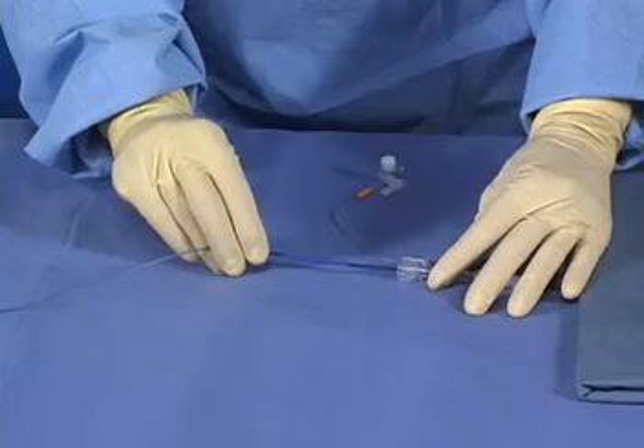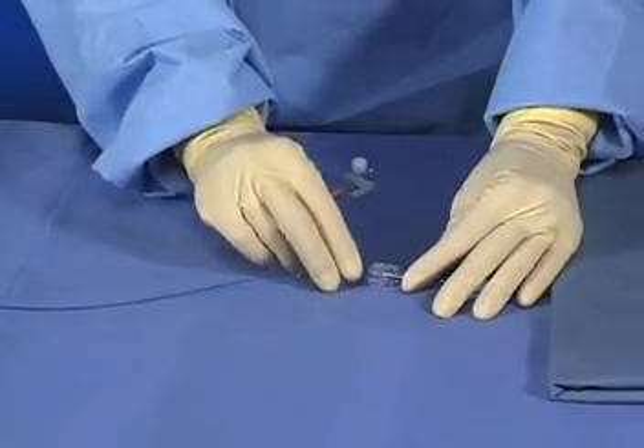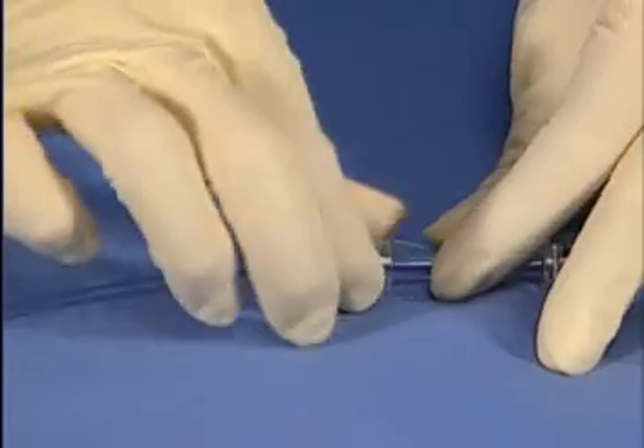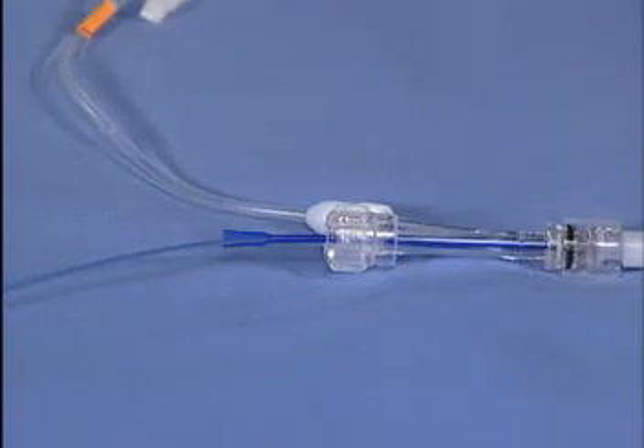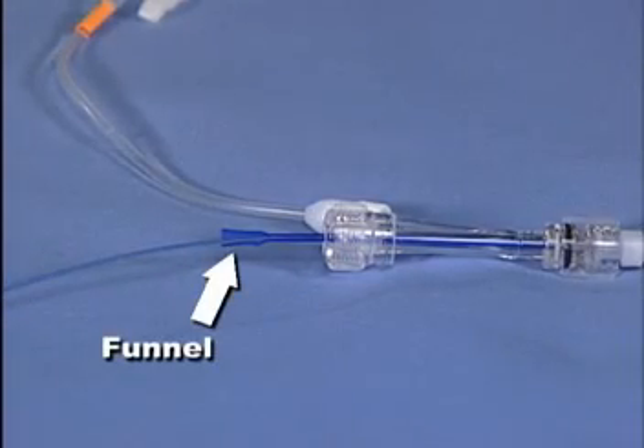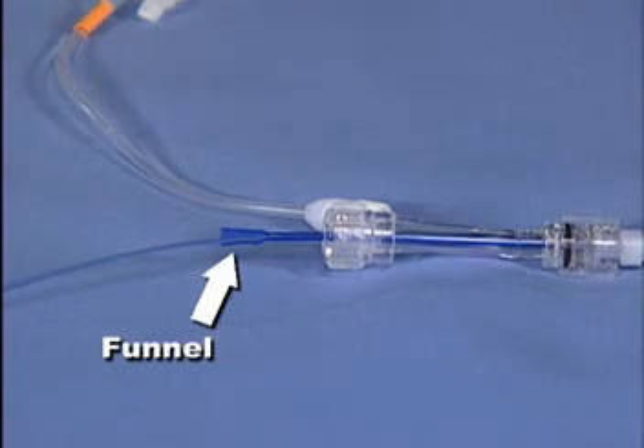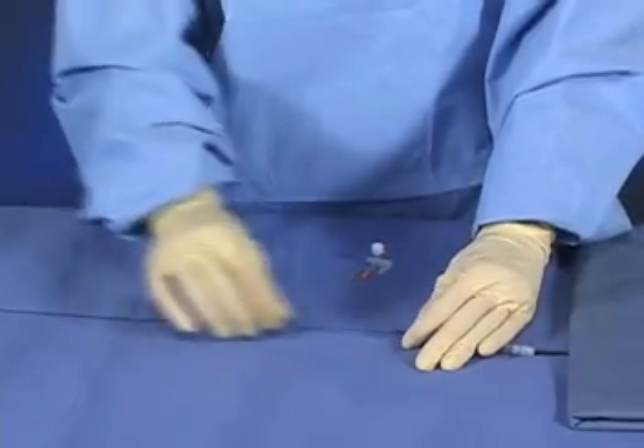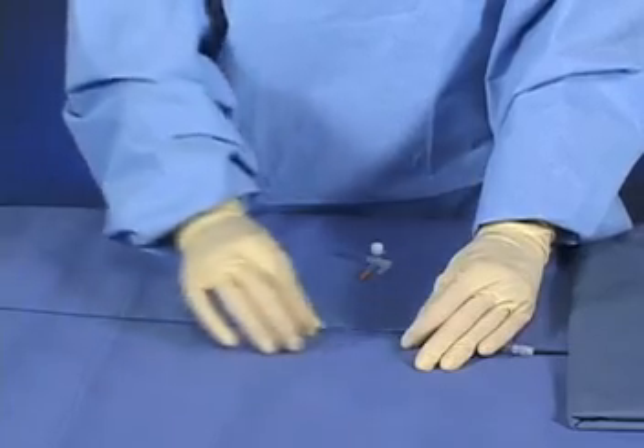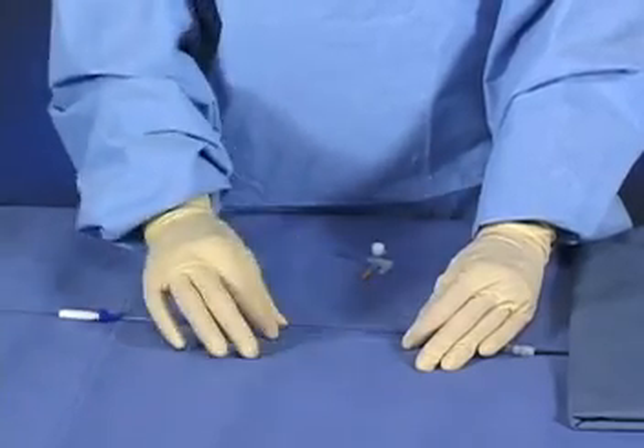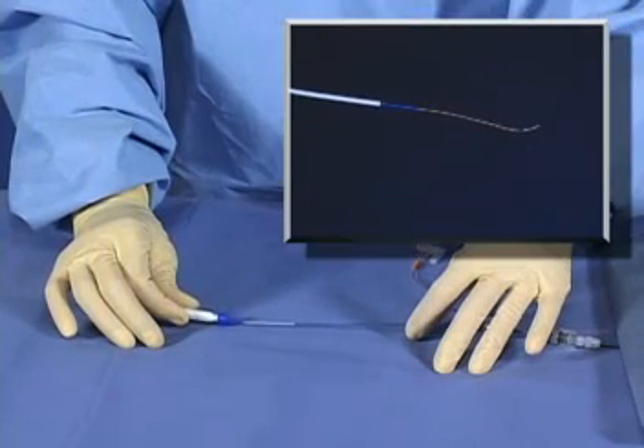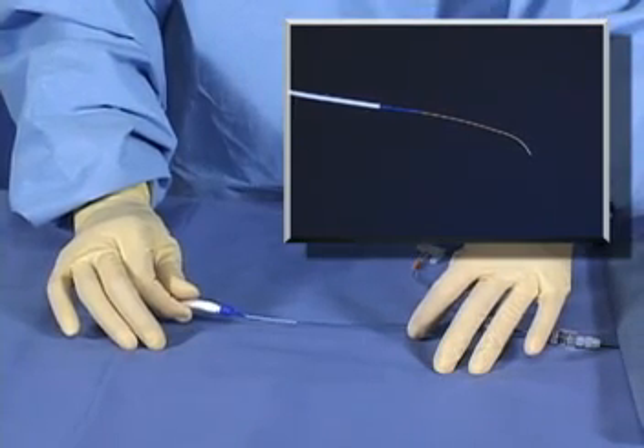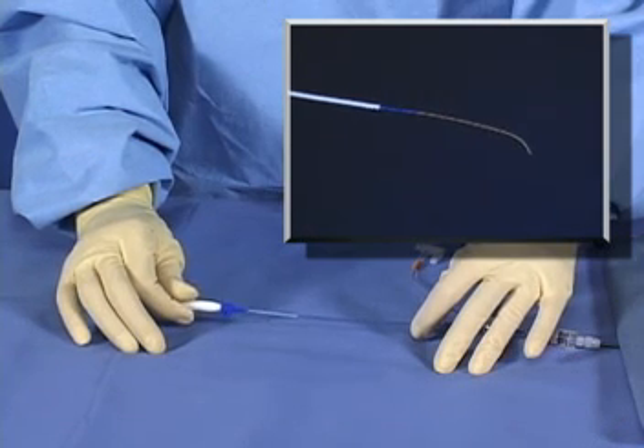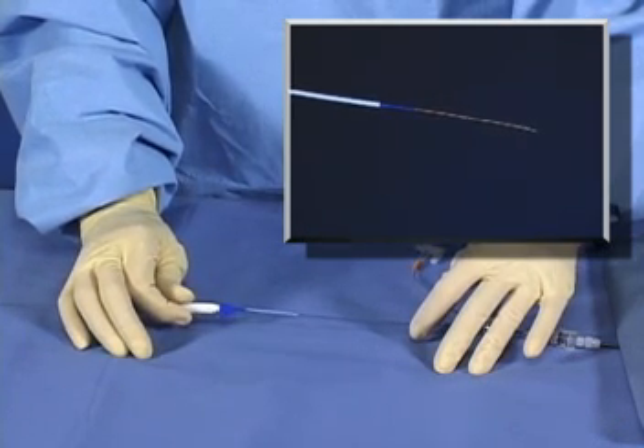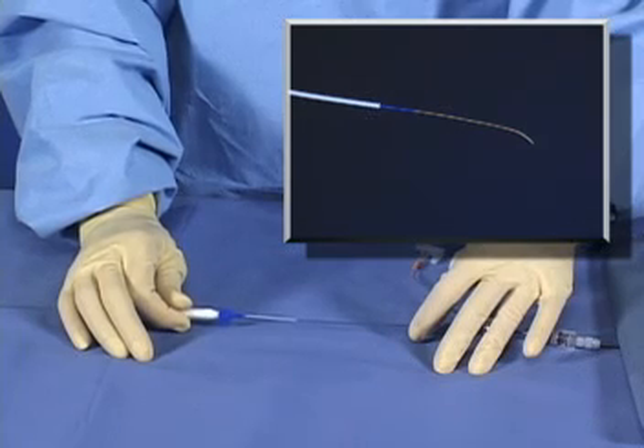Insert the introducer tool and delivery system through the hemostatic valve and guiding catheter or long sheath. Then, tighten the valve. Make sure the funnel of the introducer tool is not within the valve. Advance the delivery system through the catheter or sheath and into the desired vessel. The guide wire rotates independently from the filter basket and delivery sheath. Therefore, it is important to steer the guide wire tip with the torque device. Do not torque the delivery sheath.